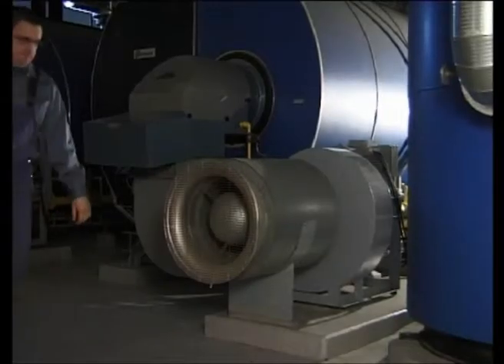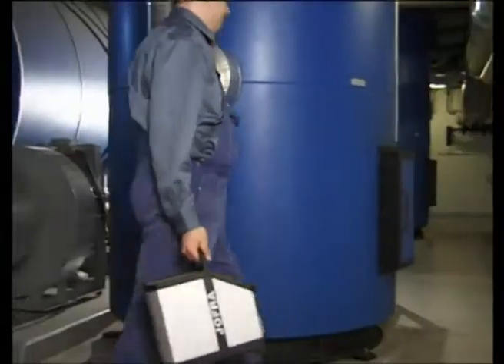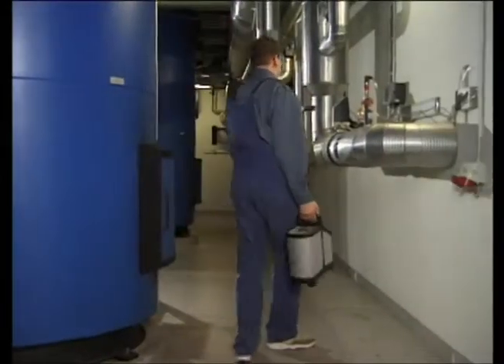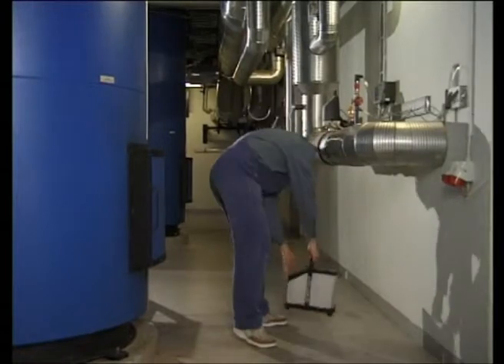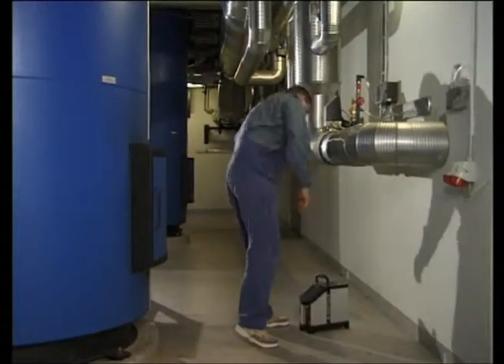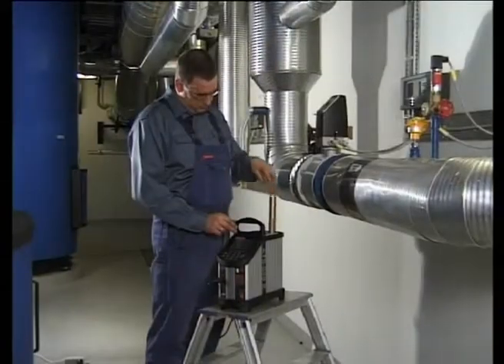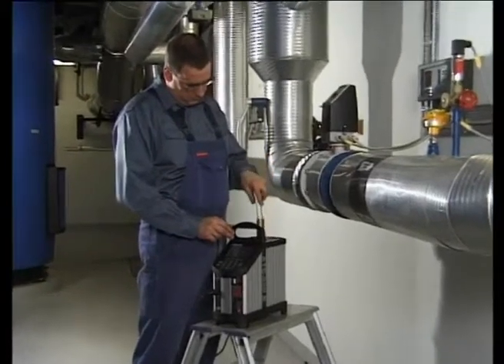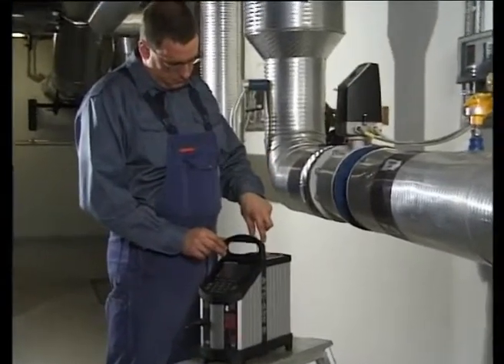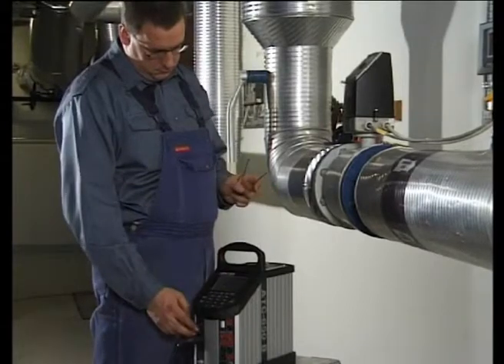The JOFRA ATC series greatly improves your calibration results. Not only does this series have a built-in reference sensor in the well, it is also equipped with an external reference thermometer, thus enabling one instrument to provide you with the freedom to perform your calibrations at the process site while maintaining a higher level of accuracy.